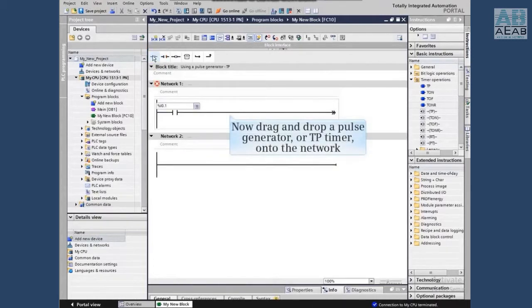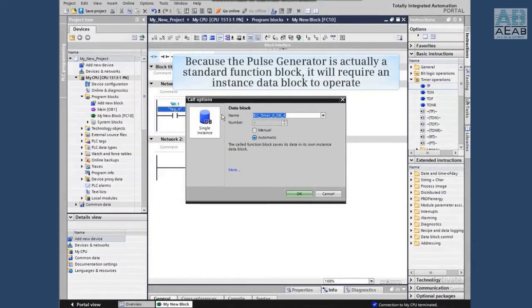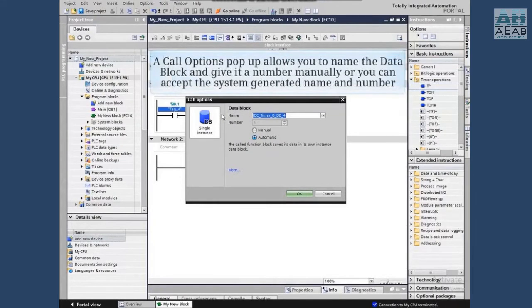Now we will drag and drop a pulse generator, or TP timer, onto the network from the basic instructions catalog. Because the pulse generator is actually a standard function block, it will require an instance data block to operate. A call option pop-up allows you to name the data block and give it a number manually.